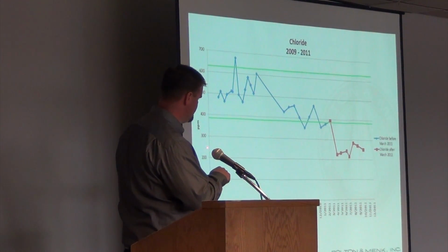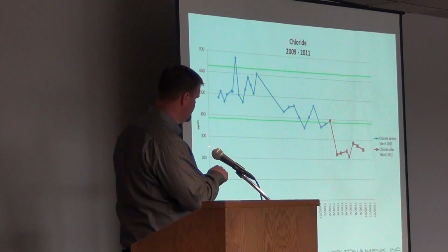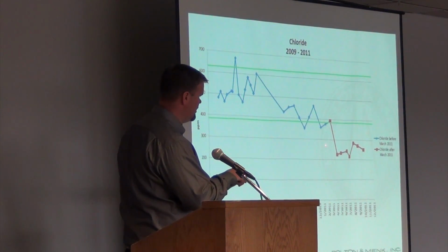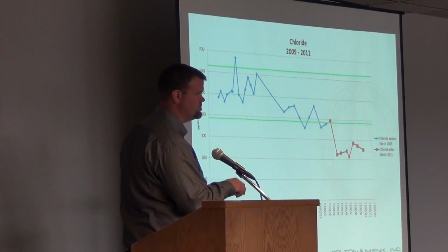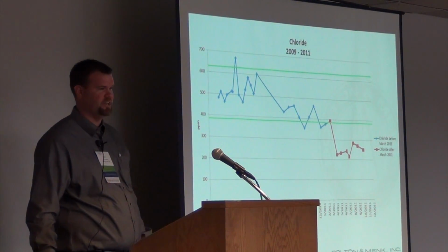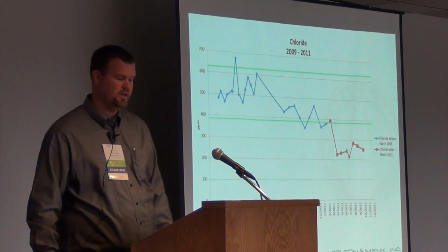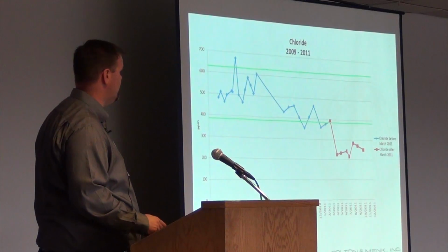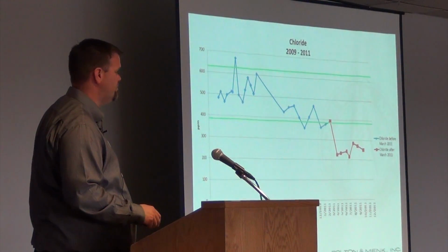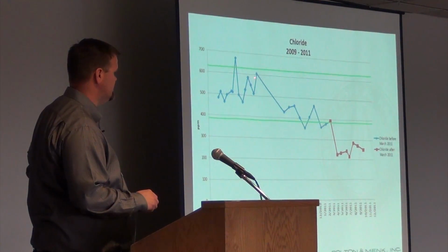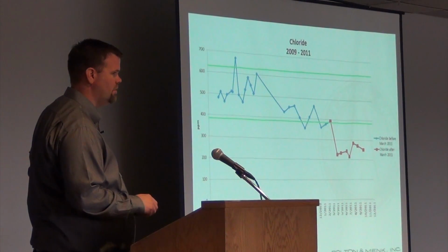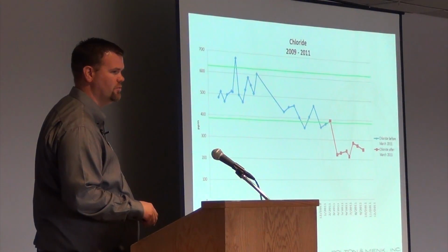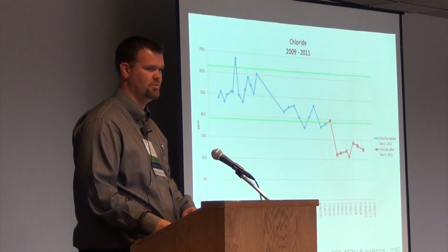The catch is that if Minnesota is around that 230, which is in here, they're still hanging right around that mark. So that might take further public education and some evaluations to see if they can go below that. But if Minnesota follows the Iowa example, it's most likely that the changes that St. Peter made at their water plant has already solved their wastewater salt discharge issue with regards to chlorides.